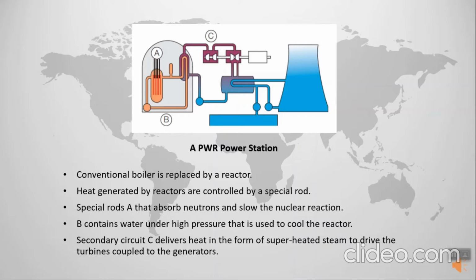The containment building houses the major difference, where a conventional boiler is replaced by a reactor. The heat generated by the reactor is controlled by special rod A, which absorbs neutrons and slows the nuclear reaction. A sealed primary circuit B contains water which is used to cool the reactor. The heat absorbed by the primary circuit is transferred to a secondary circuit C, which delivers the heat in the form of superheated steam to drive the turbines coupled to the generators. Temperature measurement is vital to both the efficient and safe operation of the heat-powered system.